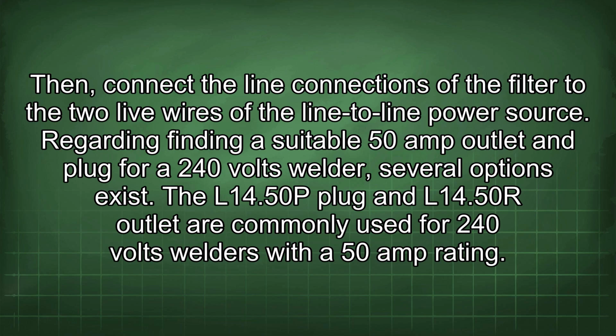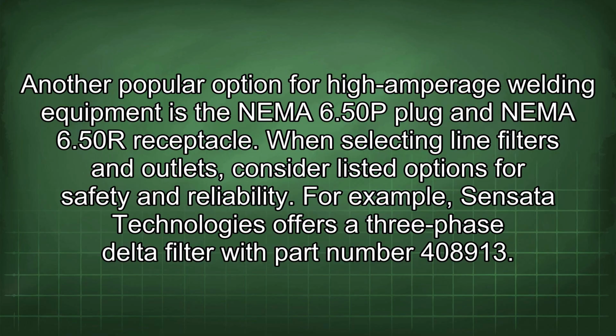The L14-50P plug and L14-50R outlet are commonly used for 240 volts welders with a 50 amp rating. Another popular option for high amperage welding equipment is the NEMA 6-50P plug and NEMA 6-50R receptacle. When selecting line filters and outlets, consider listed options for safety and reliability.